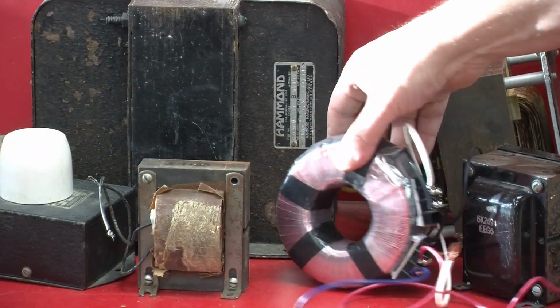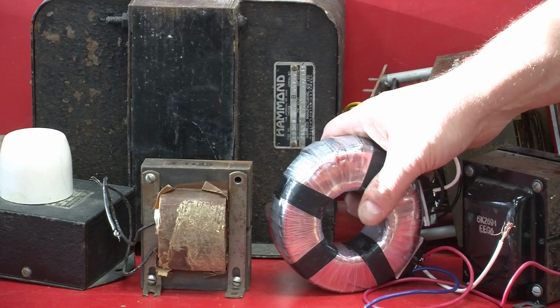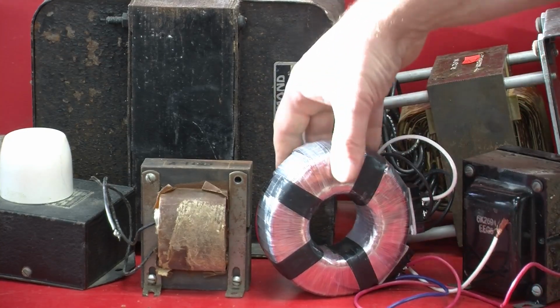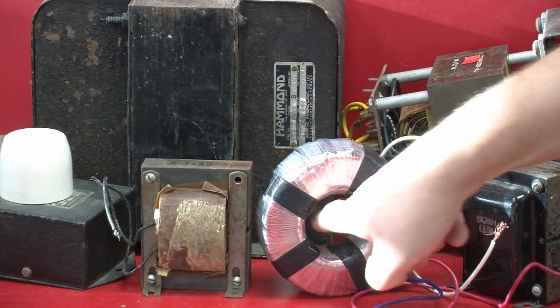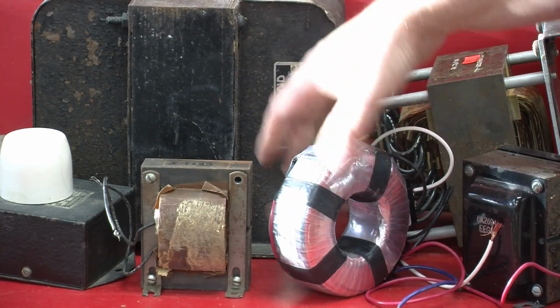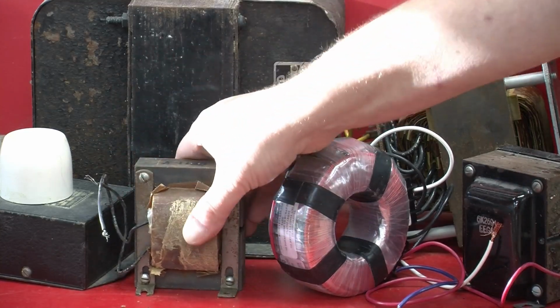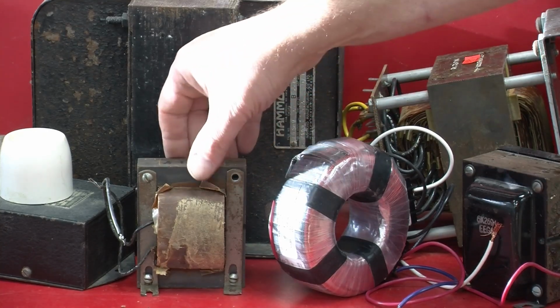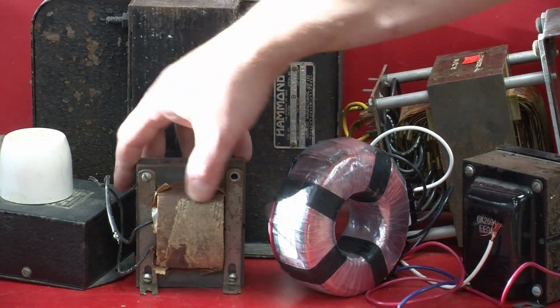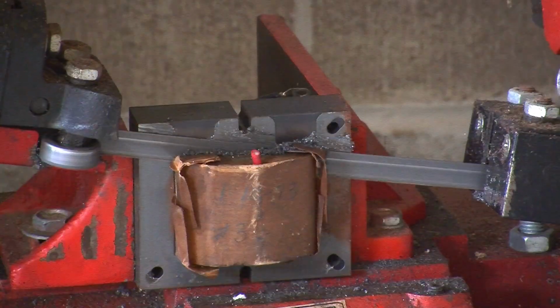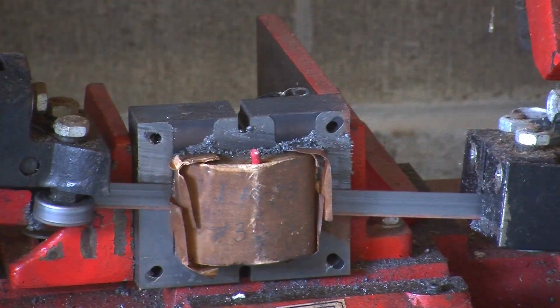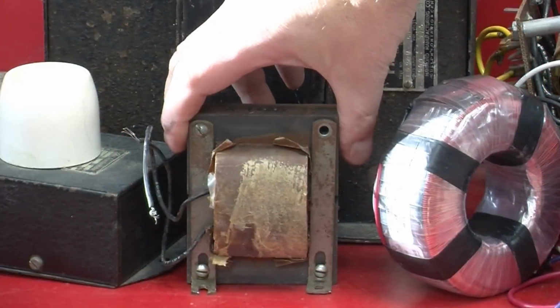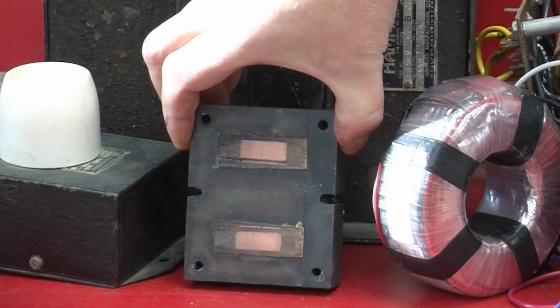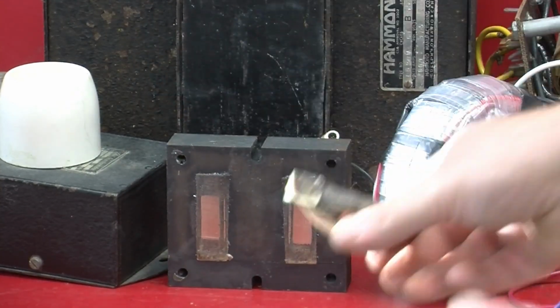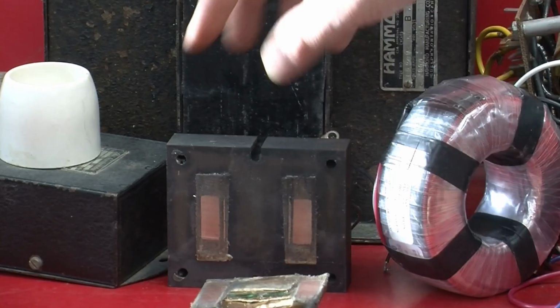So the most common transformer cores are what you can see assembled here. We've been using a toroidal transformer core because it's easy for me to stick wires through the center for our experiments, but by far the most common cores are these EI cores, which are really the cheapest type of transformer to make. And what I did was I in fact cut the windings off the side of a transformer just like that so we could take a look at it. And here it is. This is the so-called EI core, and these are the windings from it.